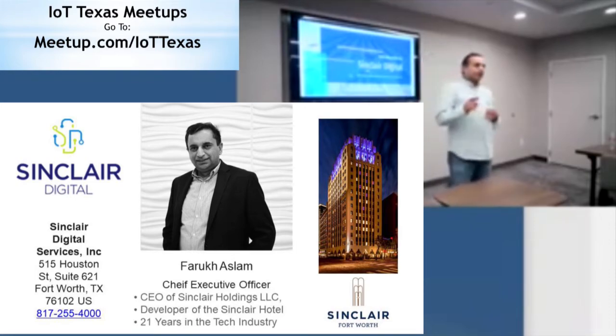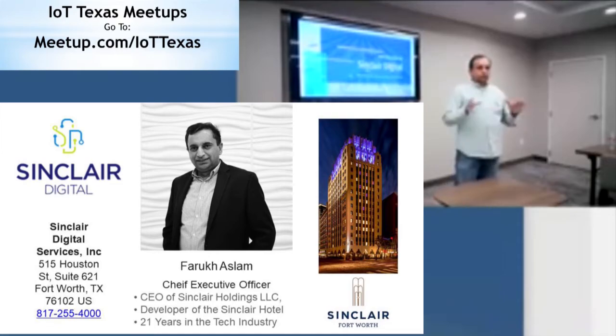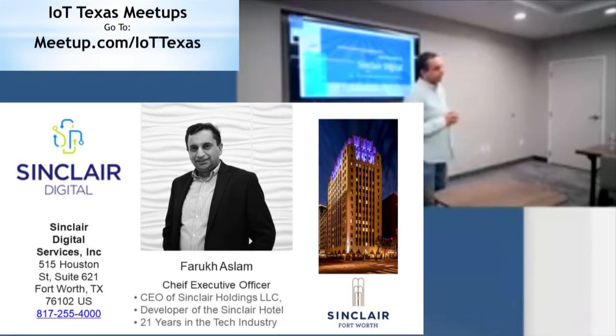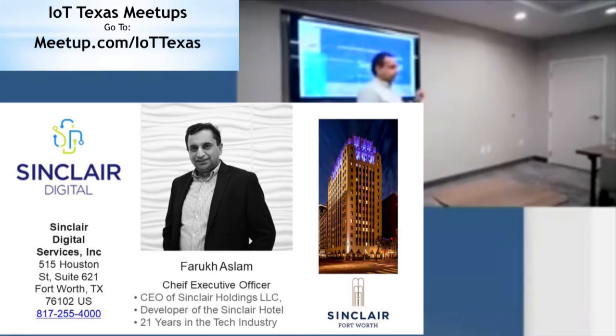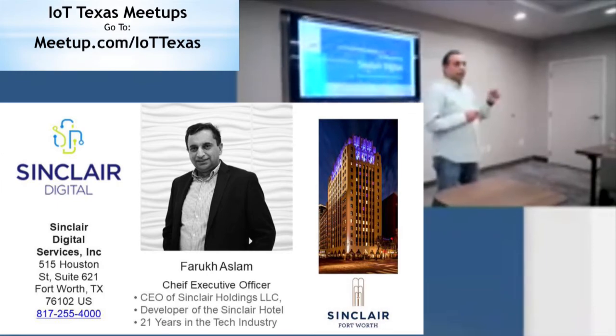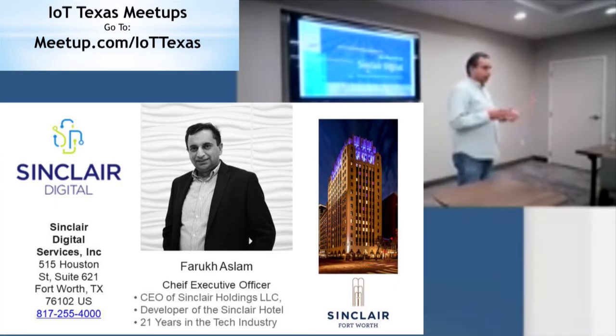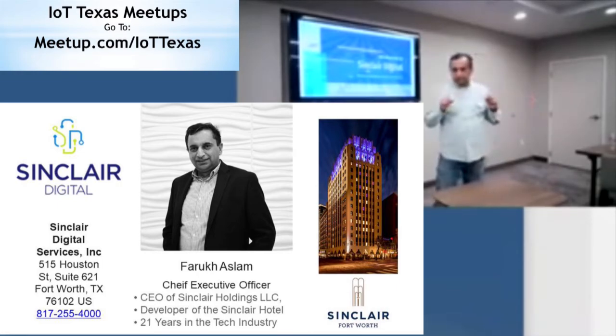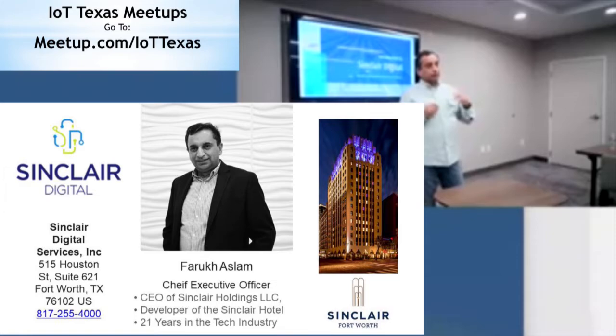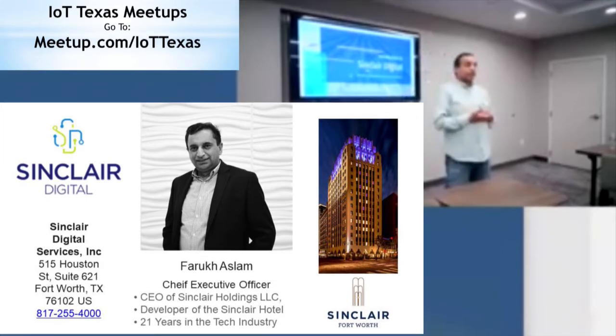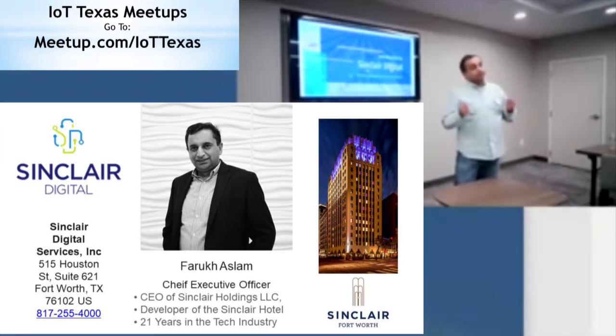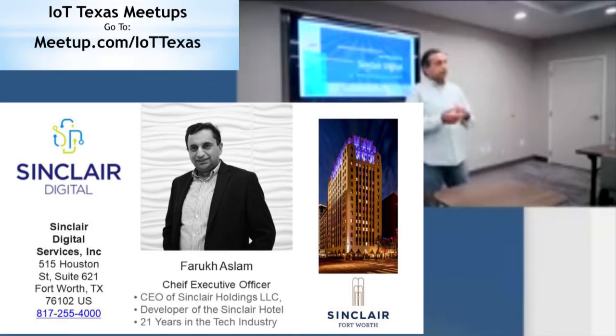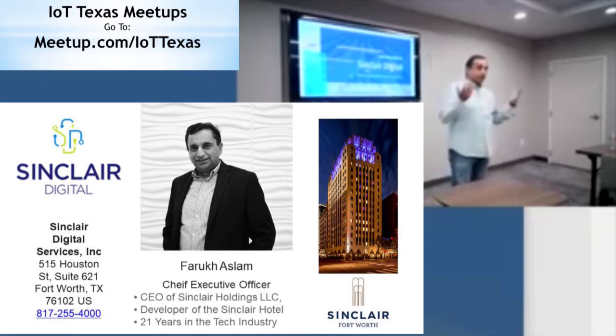At that time, the City of Fort Worth building code said office space couldn't exceed 0.8 watts per square foot of electric load per light. We monitored this with installed devices and were under 0.2 watts. So we were at a 25% level, where architects were having difficulty even achieving 0.8 watts per square foot for all the lighting, and we were performing at 0.2 watts.